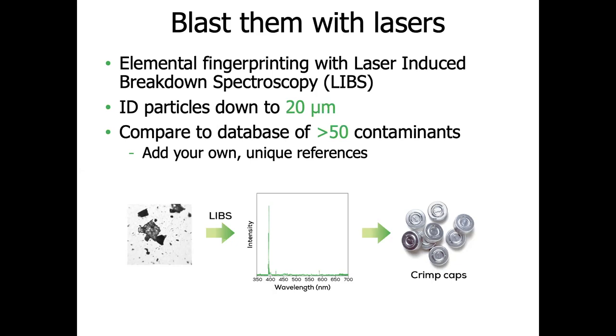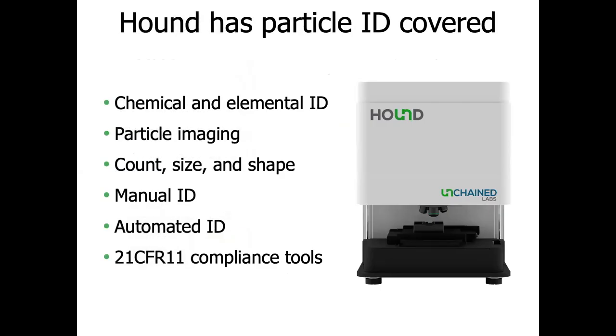By combining microscopy, Raman, and laser induced breakdown spectroscopy on a single platform, Hound lets you characterize and investigate the vast majority of particles you would realistically run into in your environment. The instrument can be used manually when you have a few particles, or in automated mode when you have tens, hundreds, or thousands. Having everything on one platform with a single sample prep and a single piece of software — where you can switch between spectroscopies with a click of a button to identify anything from protein aggregate to stainless steel — and the ability to create your own custom reference library easily could really help you accelerate the identification and work through your root cause investigation.